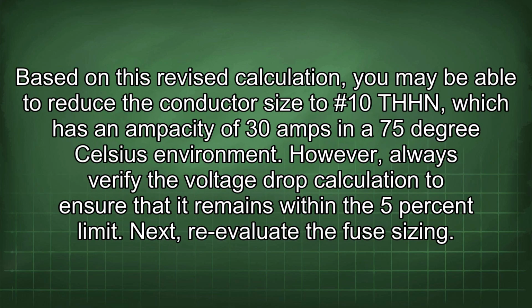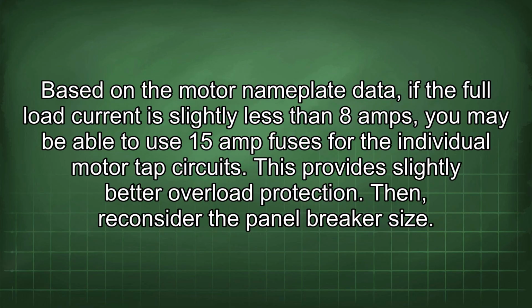Based on this revised calculation, you may be able to reduce the conductor size to #10 THHN, which has an ampacity of 30 amps in a 75°C environment. However, always verify the voltage drop calculation to ensure that it remains within the 5% limit. Next, re-evaluate the fuse sizing. Based on the motor nameplate data, if the full load current is slightly less than 8 amps, you may be able to use 15 amp fuses for the individual motor tap circuits. This provides slightly better overload protection.